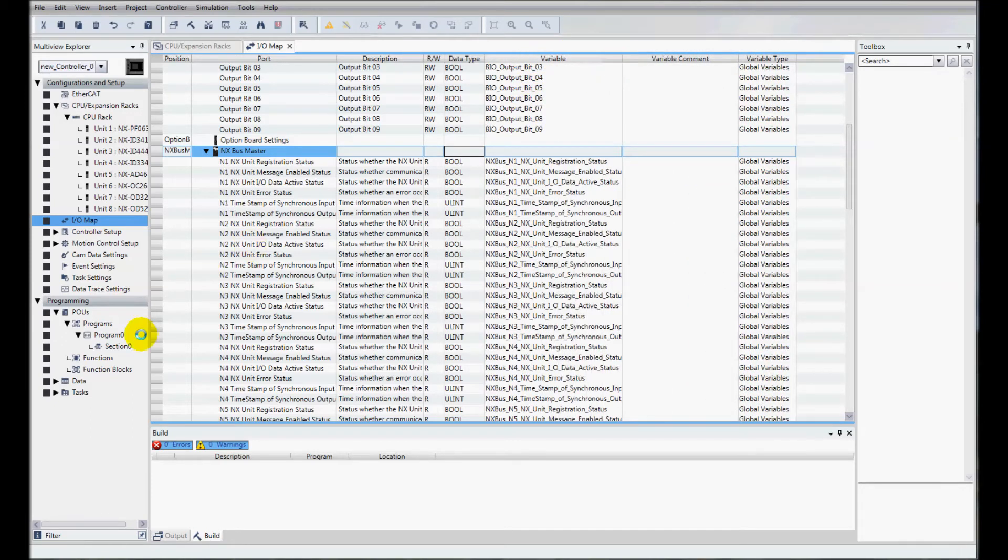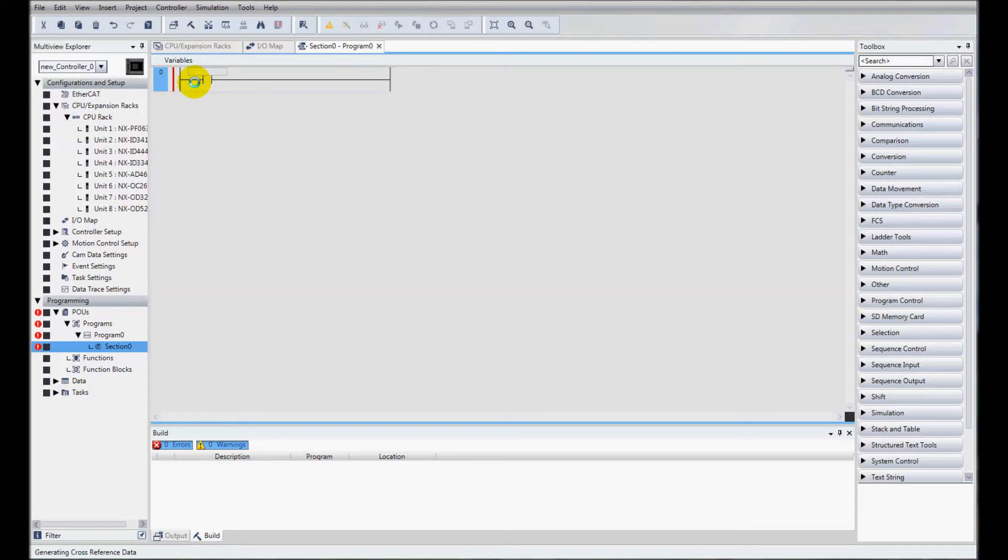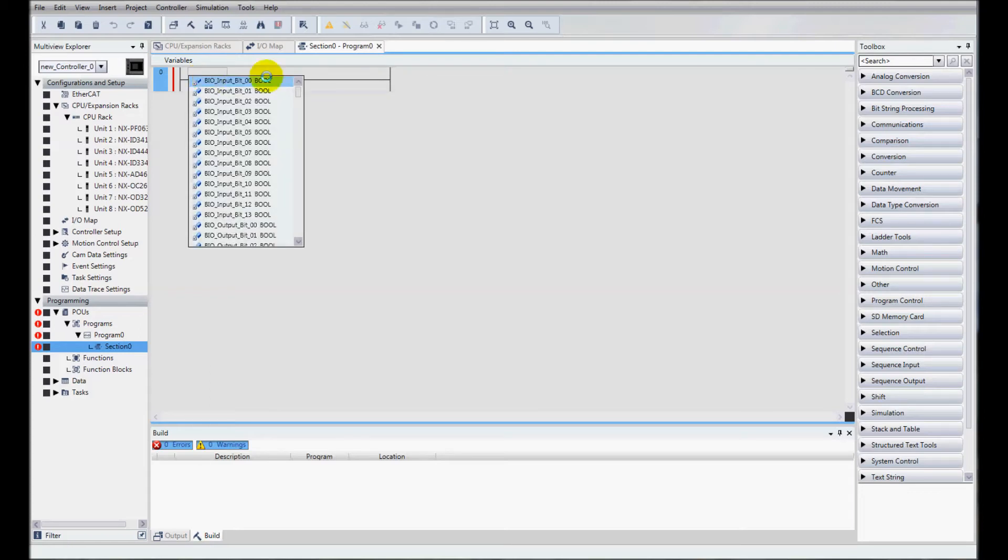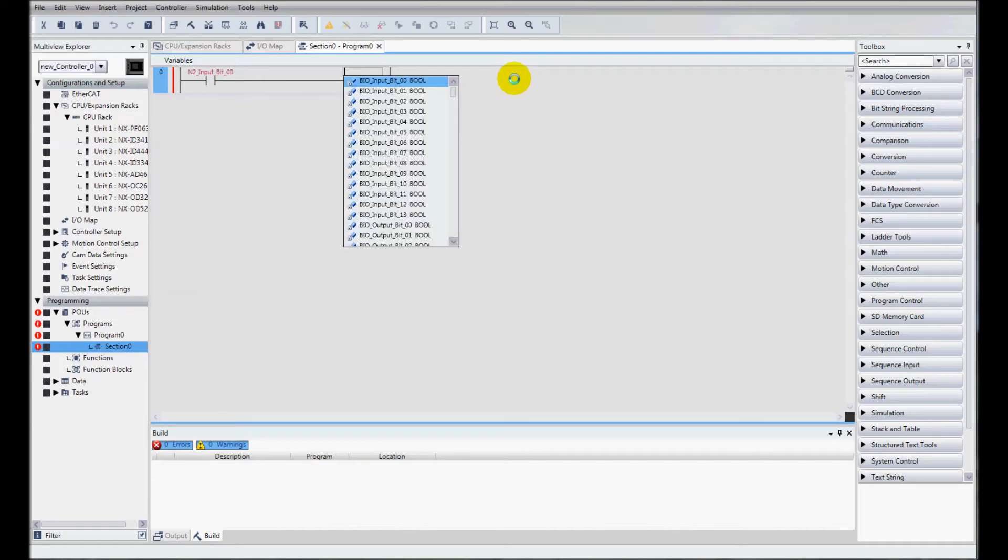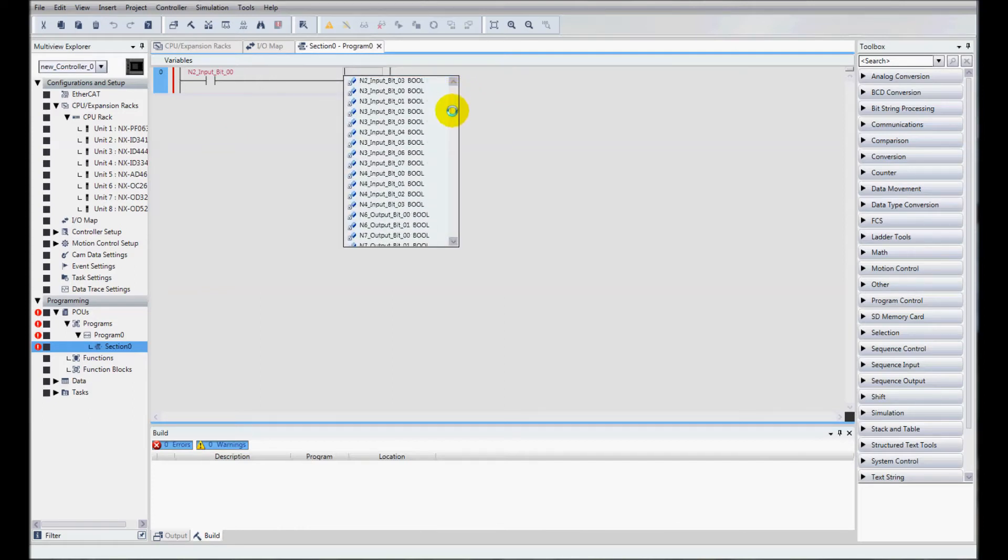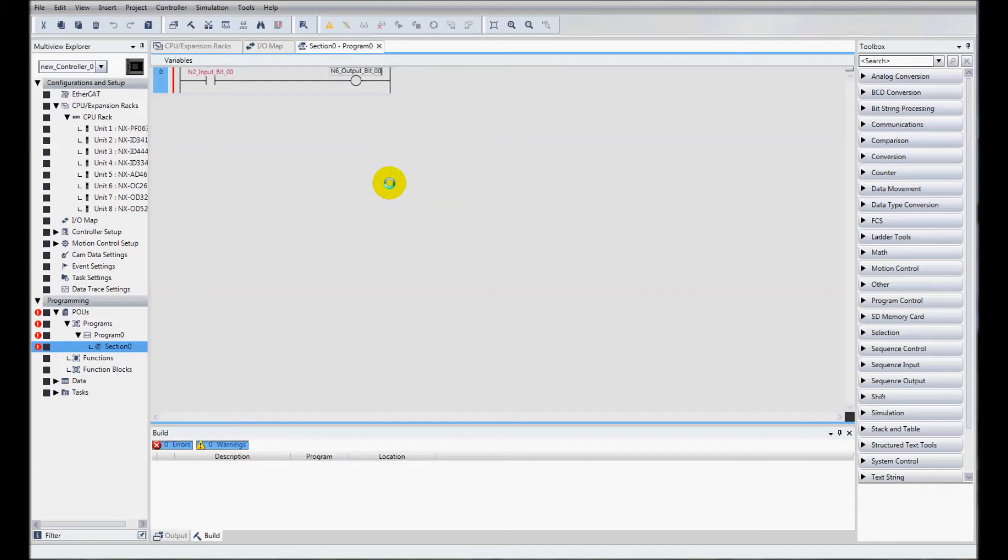Next, I'll come down to my PLC program. I'm going to add a contact by typing C, and I'll hit control space. This brings up my device variables. My first input is N2 input bit 0. Then I'll add an output by typing O, and I'll go down to N6 bit 0, which is my OC, my relay output.